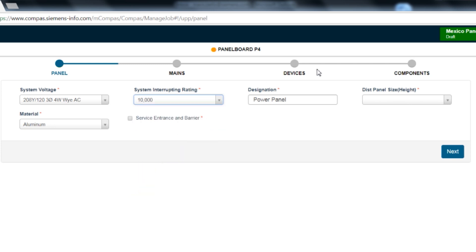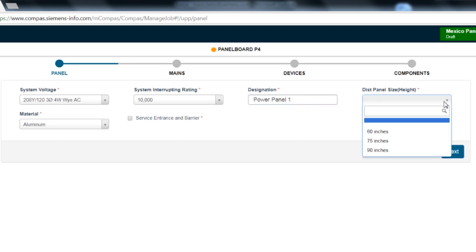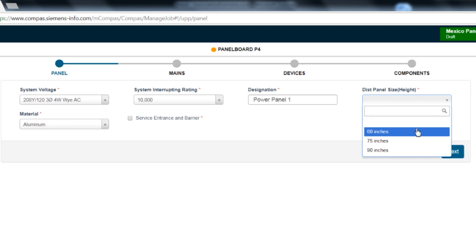The next box allows you to name the power panel. The height selection allows you to pick the size of the panel you wish to use. The 60 and 75-inch height panels drive to a P4 panel and the 90-inch height drives you to a P5 panel. Use the 90-inch P5 panel if you have fuse switches over 200 amps or if you would like to dual-mount 400 amp breakers.